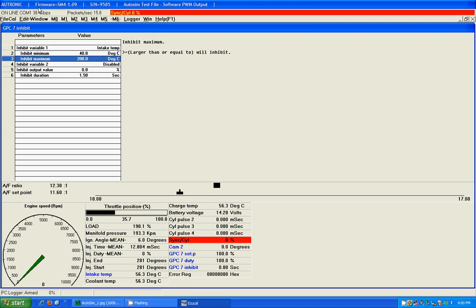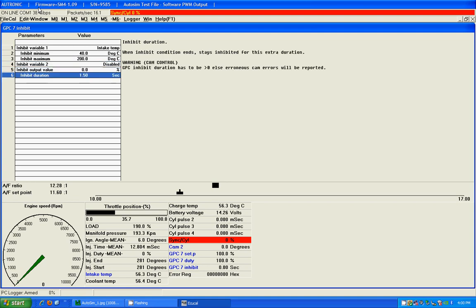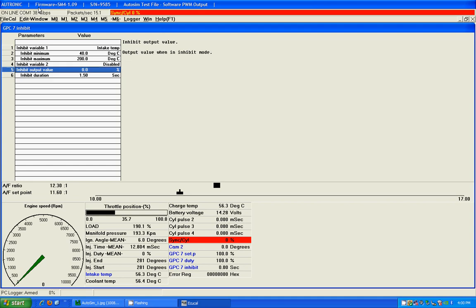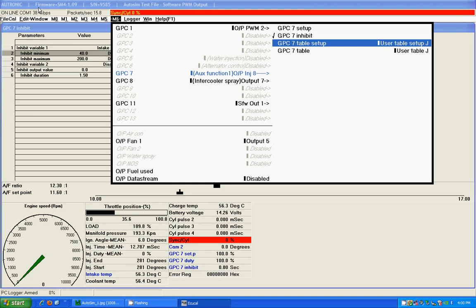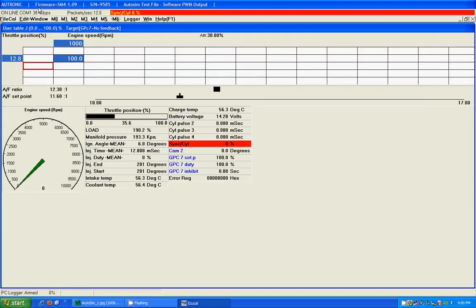We can go down here now and set an inhibit duration, which means that once the inhibit value has ended, the output will still stay disabled for this amount of time. It allows for a fan not to cycle on and off in a split second, because it's hovering between those two temperatures. So in this case, it's set to 1.5 seconds. So what happens here now is that when your intake temperature is 40 degrees and above, your fan is on. When it drops below 40, your fan is off. And once your fan turns off, even when it goes above 40, it won't turn back on for another 1.5 seconds. To get this function to work, we still need to have a table, because what we basically want to do with this table is have a single site, which means that no matter what the condition is, it's always on. So we have 100% in here, which means that the fan is always on except when the inhibit occurs, then it turns off.